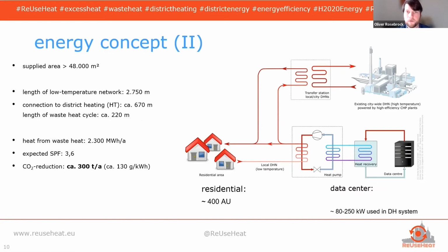There was the end of the existing district heating network, while the energy generation was right beside the data center, and therefore the connection from the district heating network towards the new energy plant needed to be quite long. We expect to get something like 2,300 megawatt hours per year out of the waste heat. We expect an SPF, so efficiency of the heat pump, of 3.6. And in the end, we hopefully can reduce the CO2 emissions by up to 300 tons per year, which is a quite good number. So a reduction of 130 grams per kilowatt hour. So a very low value in the end.